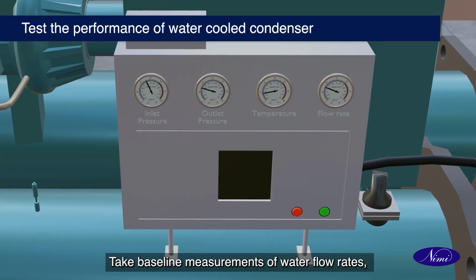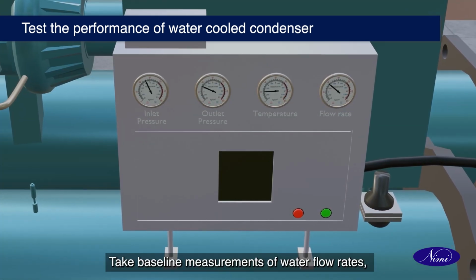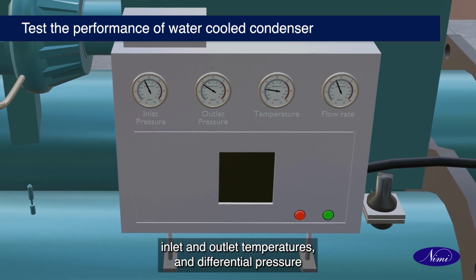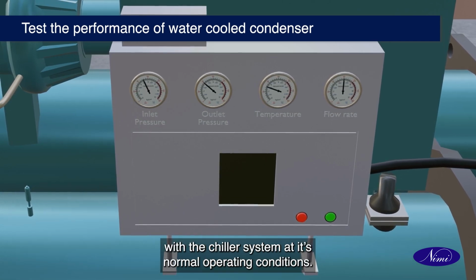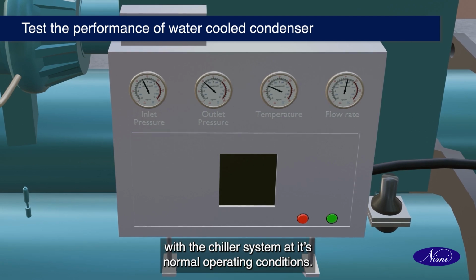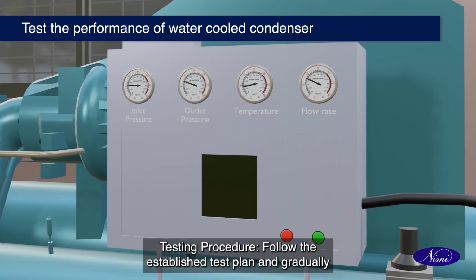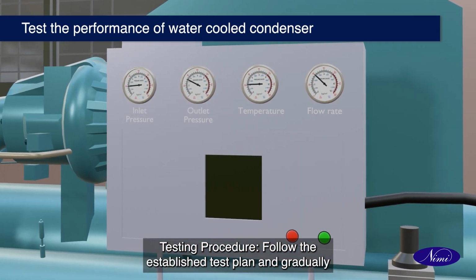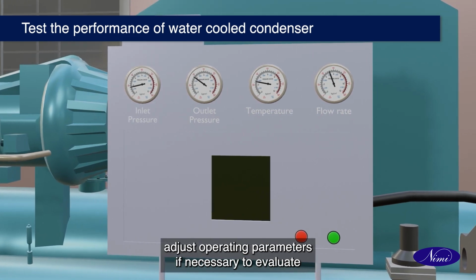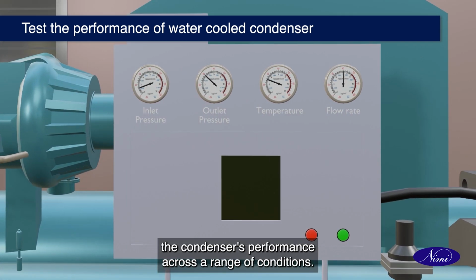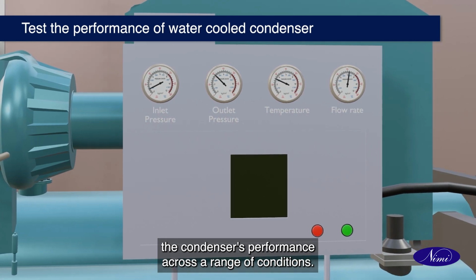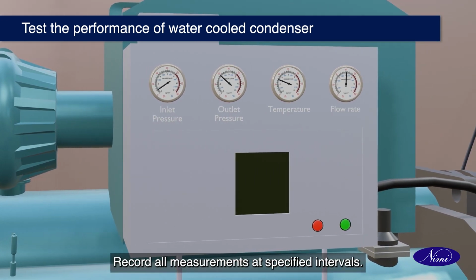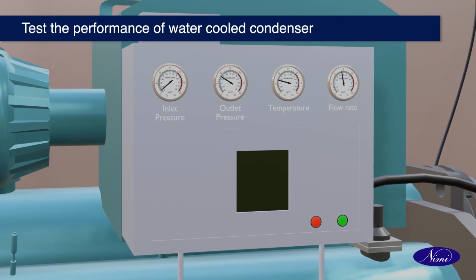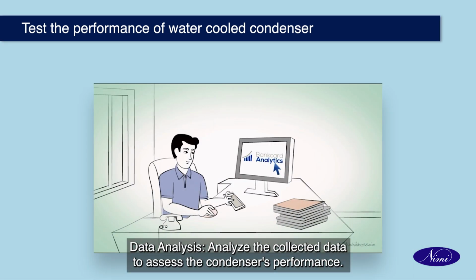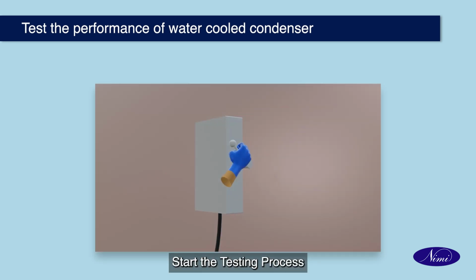Baseline measurements. Take baseline measurements of water flow rates, inlet and outlet temperatures, the differential pressure with the chiller system at its normal operating conditions. Testing procedure. Follow the established test plan and gradually adjust operating parameters if necessary to evaluate the condenser's performance across a range of conditions. Record all measurements at specified intervals. Data analysis. Analyze the collected data to assess the condenser's performance. Start the testing process.